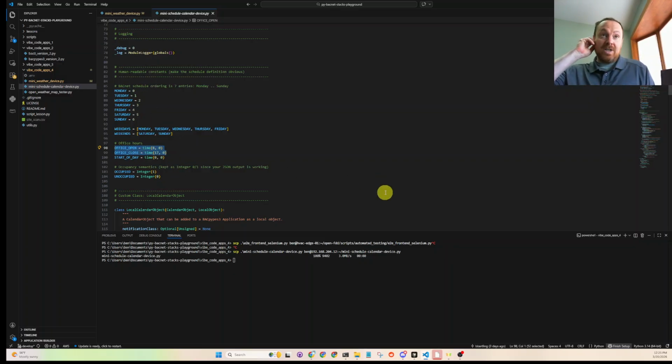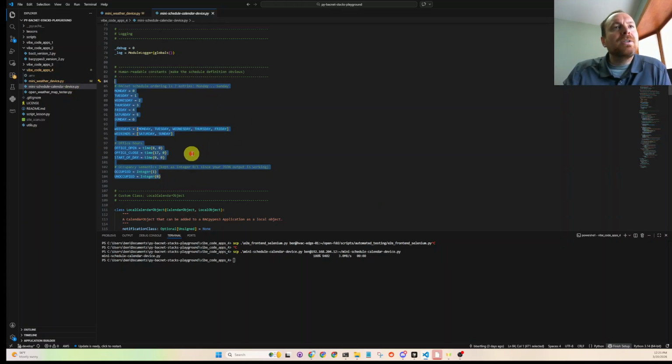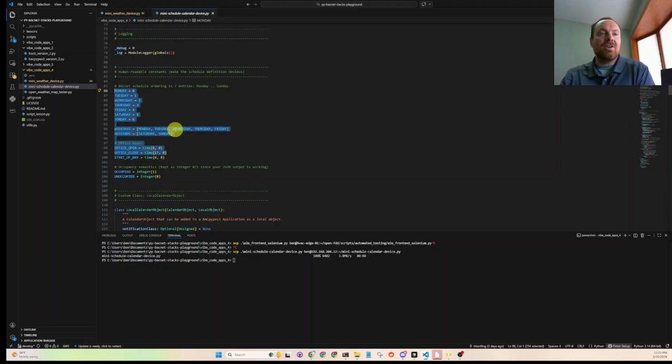But maybe I'll try and bring up how it might look on the building automation front end, where there's just a generic weekly run schedule. So this is ultimately what we're trying to mimic and study a little bit behind the scenes. And you probably would run into this in the wild on building automation systems. It might not be guaranteed that they have this, but I've seen some manufacturers support this right out of the box, where you set the runtime of the equipment through the building automation system, and then you'll see a BACnet object representing that data.